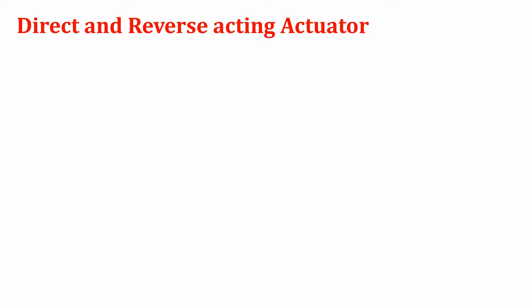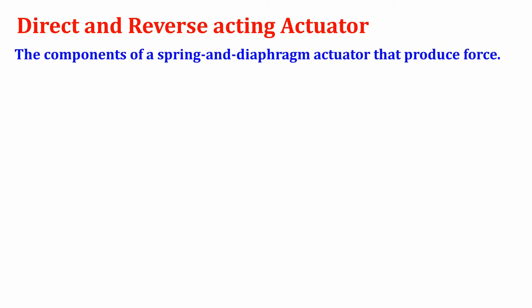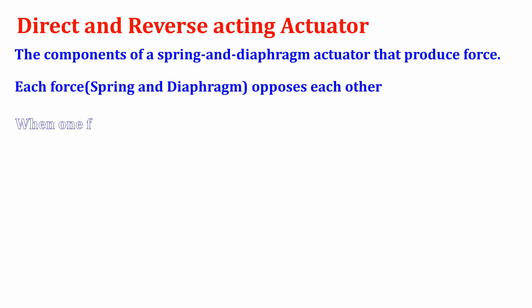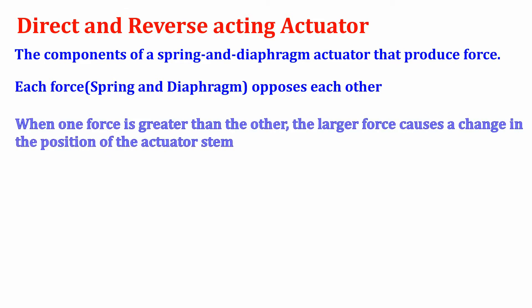There are two different types of actuators: the direct acting actuator and the reverse acting actuator. In an actuator we have two different forces — the force supplied by the spring and the force supplied by the diaphragm. If the spring force is higher, the spring takes control of the operation; if the diaphragm force is higher, the diaphragm takes control. Using this principle, we derive these two actuator types.